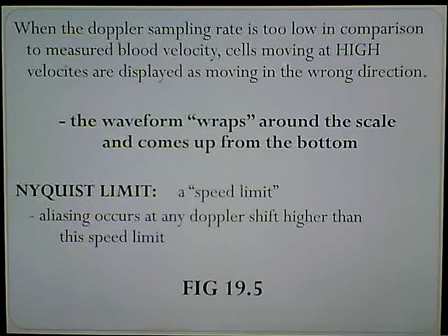There's something called the Nyquist limit. Remember the speed limit that I talked about earlier? That is exactly what this is. It is a speed limit. Aliasing occurs at any Doppler shift higher than this speed limit.